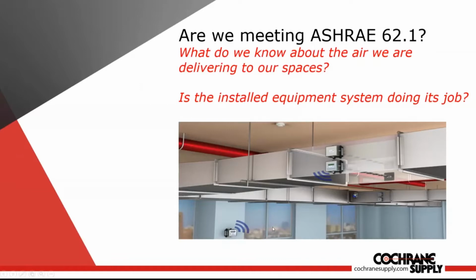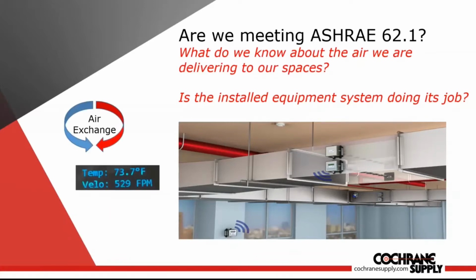So the question about airflow that we have to ask, and it's becoming more and more important in the current situation, is are we meeting ASHRAE 62.1? What do we know about the air that we are delivering to our spaces? Is the installed equipment doing what it's supposed to do? Is it getting the right amount of air to the right space? Are we getting the air exchange that we expect? Is it the right temperature? And in that duct, is it going the speed it's supposed to be going to provide that air exchange?